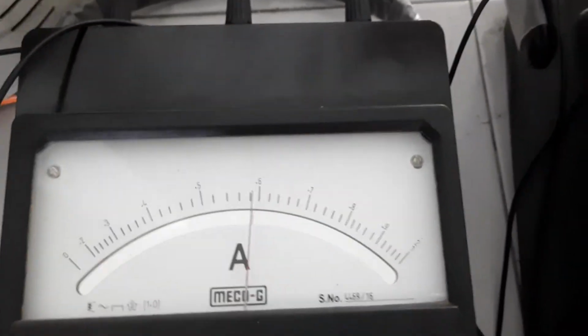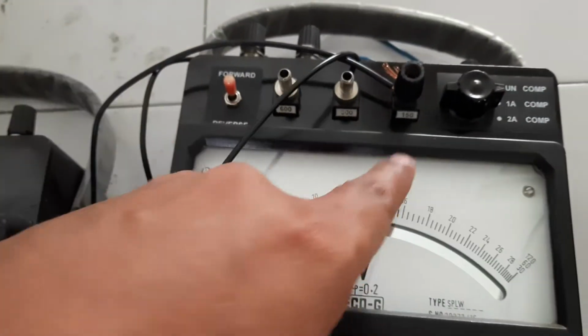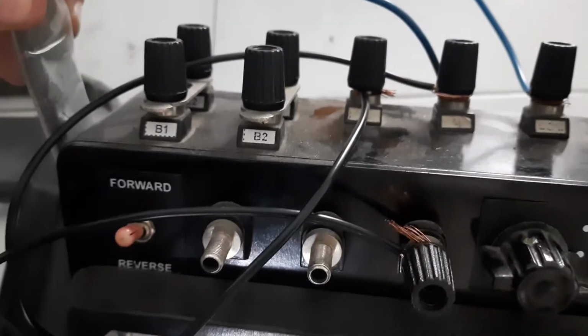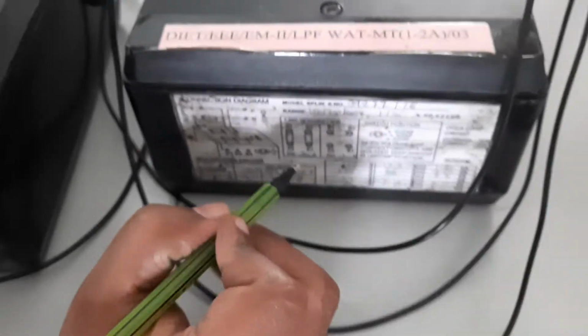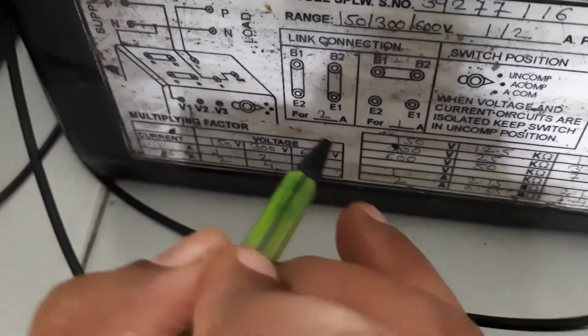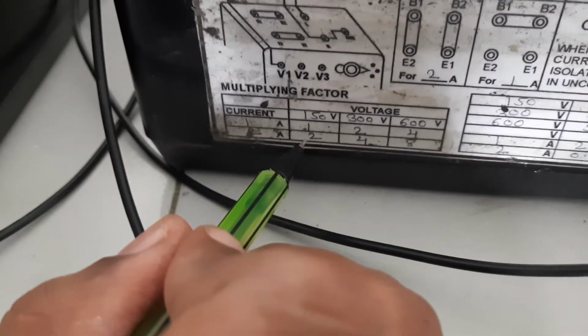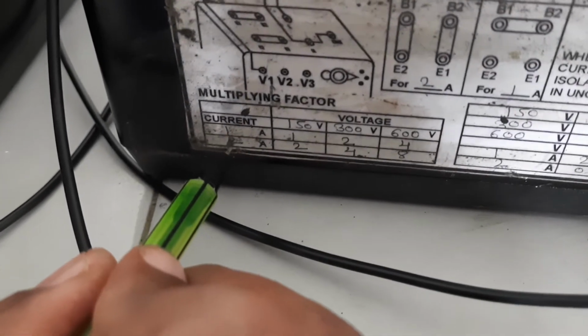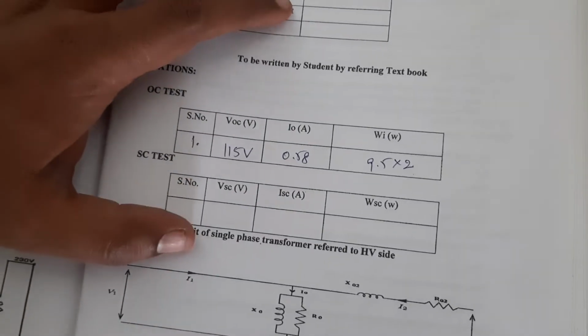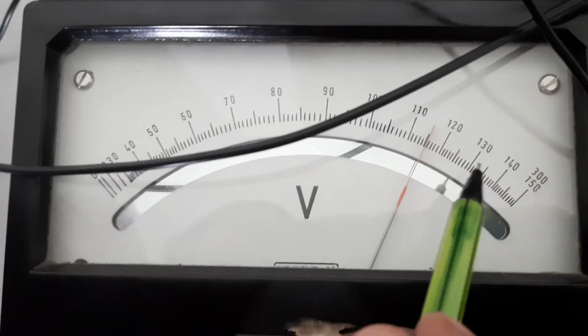You have to remember we have a multiplication factor here. The wattmeter we connected is 150, and we have to check the connections, that is B1 E2 and B2 E1. The current range is 2 amperes, so we have to check how much voltage we have connected. We have connected 150 volts. So with 2 amperes and 150 volts, the multiplication factor is 2. Dear students, it is 2. So whatever reading we got must be multiplied by 2. Similarly, we have to check the voltmeter. The voltmeter is connected to 150, so the scale is about 150, and we need not have any multiplication factor here. Whatever reading we got is the accurate reading. This is about the OC test.